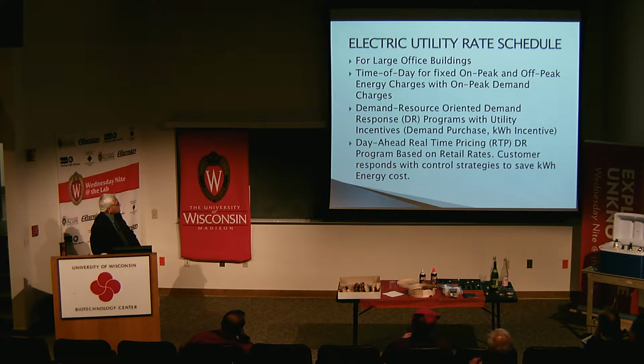Other types of demand response programs, there are several flavors offered by different utilities depending upon their load, their type of customer and so on. I'm just indicating a few. One is called resource-oriented demand response program with utility incentives. Here, for example, if the customer offers the utility that I will take off 2 megawatts of your load, the utility pays the customer so many dollars per megawatt shifted away from the utility to the customer. Or the utility may pay for kilowatt hour energy savings. If they save so many kilowatt hours, they will get so many cents per kilowatt hour.